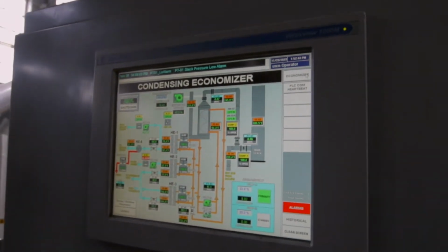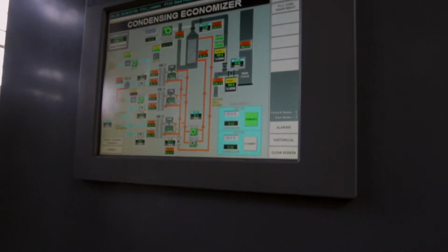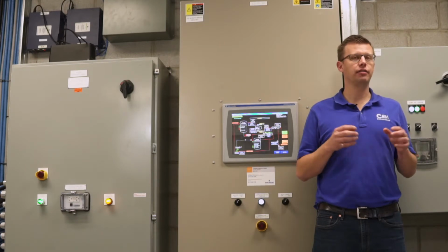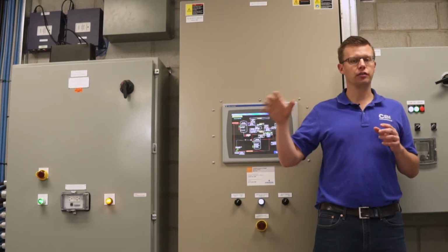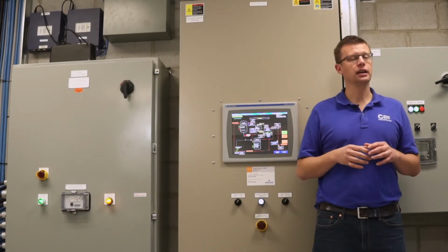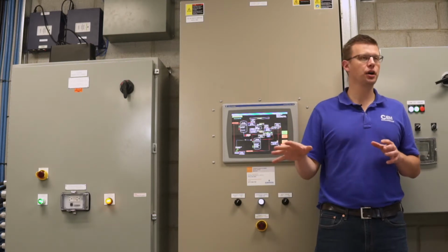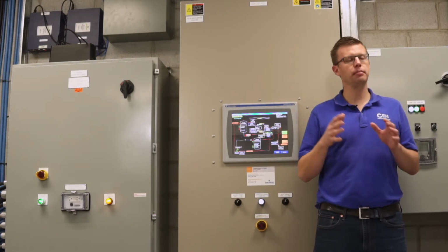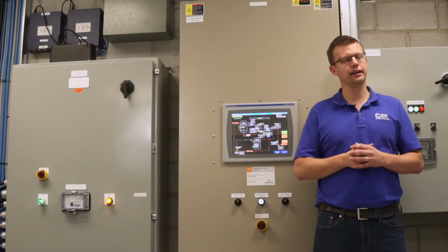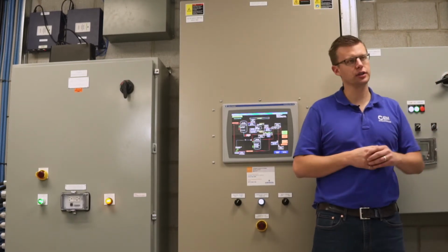It also allows load shedding. So this plant is equipped with load shedding, so that if they have to get rid of load in an islanding event, the system will automatically shed some non-critical loads so that the turbine can meet the critical load of the plant in the event of a grid failure, for example.